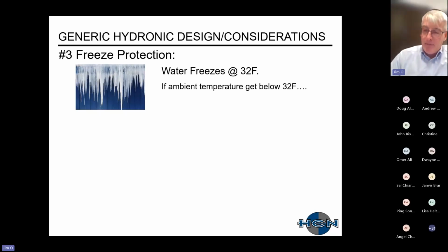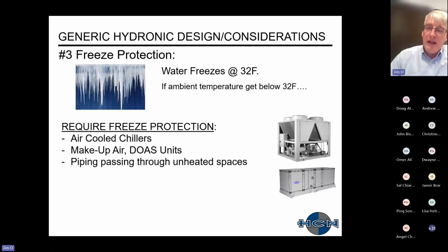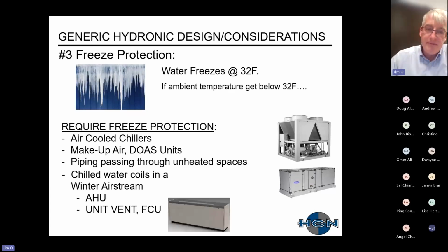If your ambient temperature gets below 32 degrees, you should add some type of freeze protection. One of the options you can do is add freeze protection to your chilled water system. Could be even hot water, et cetera. Equipment that requires freeze protection could be air-cooled chillers, make-up air units, DOAS units. Also consider piping if it's passing through any unheated spaces.